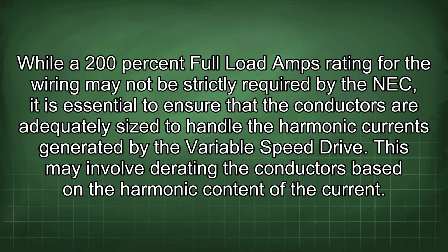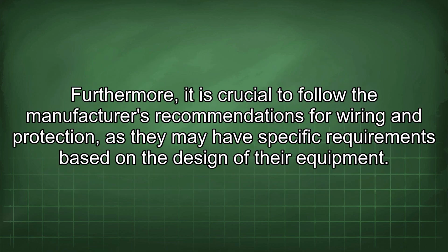While 200% full load amps rating for the wiring may not be strictly required by the NEC, it is essential to ensure that the conductors are adequately sized to handle the harmonic currents generated by the variable speed drive. This may involve derating the conductors based on the harmonic content of the current. Furthermore, it is crucial to follow the manufacturer's recommendations for wiring and protection, as they may have specific requirements based on the design of their equipment.